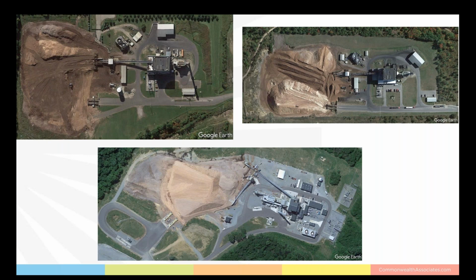In addition to the storage space, there also needs to be accommodations for the conveyors to move the fuel from the reclaim hopper near the pile to the boiler house. In the top 2 examples, there's approximately 400 feet between the boiler house and the reclaim hopper. In the bottom picture, the main conveyor is approximately 600 feet from the hopper to the boiler house. When burning biofuels such as wood pulp or crop residue, there will be ash from the burning process that falls into the bottom of the boiler and needs to be removed. That will add ash handling and removal equipment to the interior of the plant, as well as ash removal access and temporary storage to the site itself.